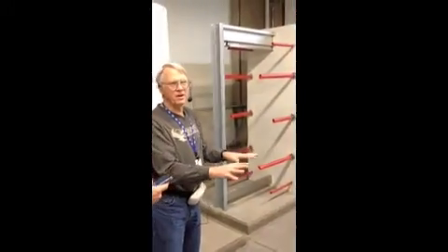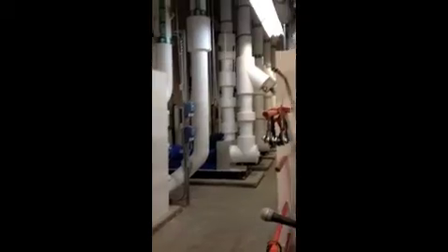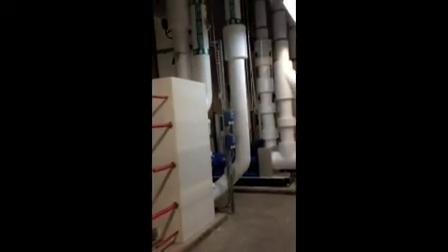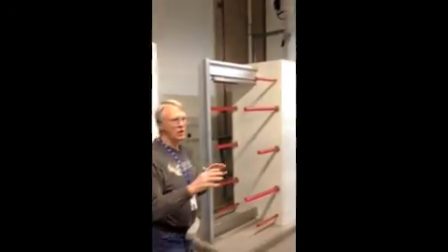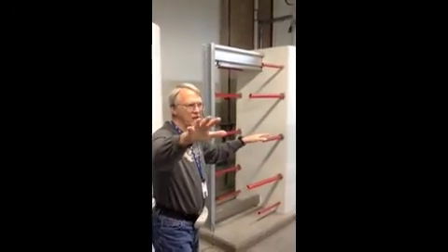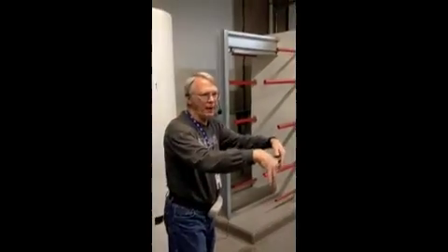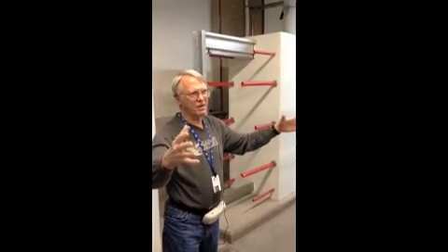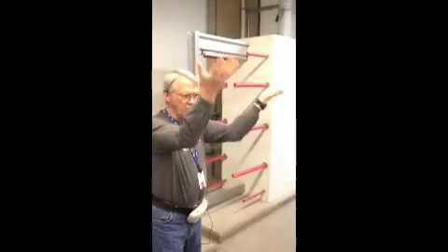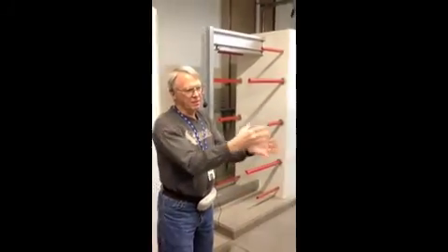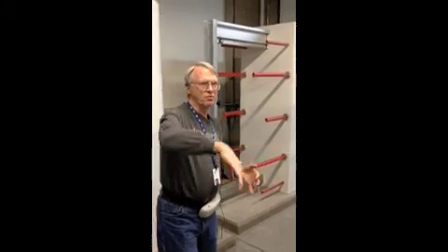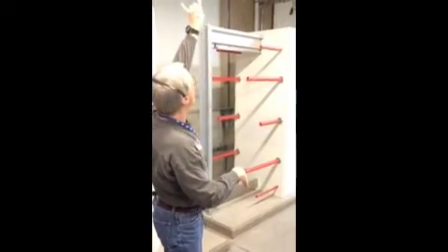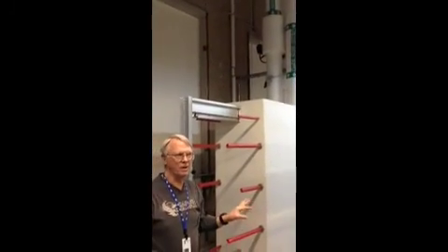We were talking a little earlier about redundancy. This is another area where we have 1 loop, although we do have 4 pumps feeding it. And it branches off from here like a tree to go out to the various areas of the data center, then down to each individual CRAC, where the chilled water goes through a radiator type apparatus in the CRAC, blows air through it, and then the heated water goes back in the same direction and comes back out through there, back into the heat exchanger to be chilled again.